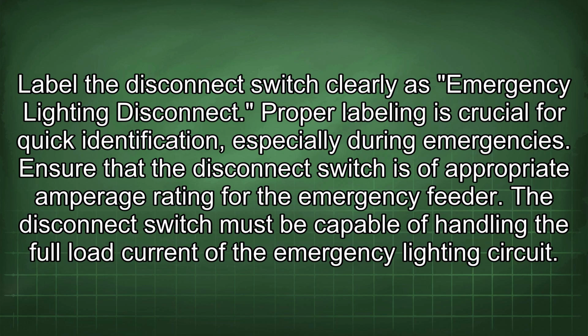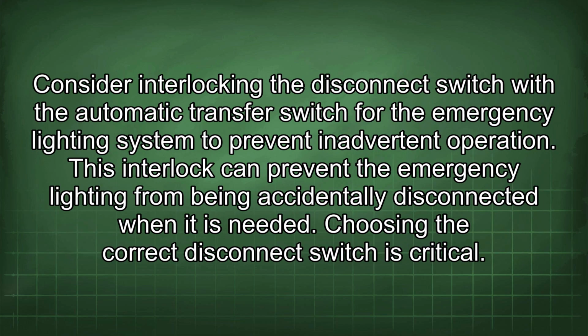Ensure that the disconnect switch is of appropriate amperage rating for the emergency feeder. The disconnect switch must be capable of handling the full load current of the emergency lighting circuit. Consider interlocking the disconnect switch with the automatic transfer switch for the emergency lighting system to prevent an inadvertent operation. This interlock can prevent the emergency lighting from being accidentally disconnected when it is needed.